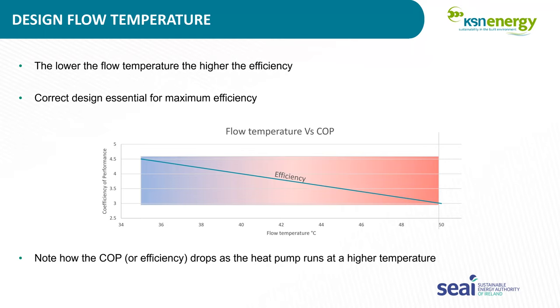And basically what that means is, if we take a COP equal to three, for every unit of electricity that goes into the heat pump, you get 3 units of heat back out of it. Every heat pump is slightly different and dependent on the refrigerant and a lot of other factors. But just as a typical example, for this heat pump, if the flow temperature was run at 35 degrees, for every unit of electricity you're going to get 4.5 units of heat coming back from it. Whereas if we wanted to run it at 50 degrees flow temperature, we're only getting a COP of 3.